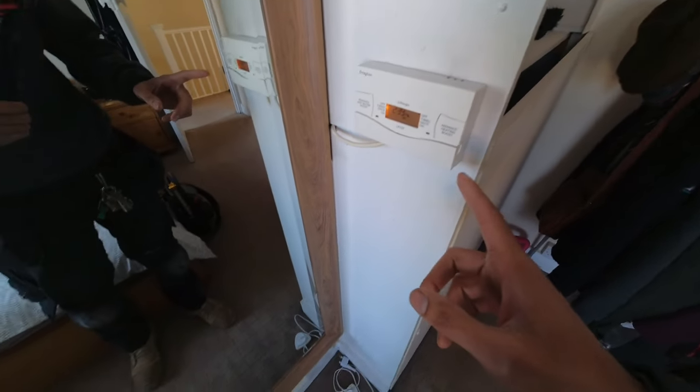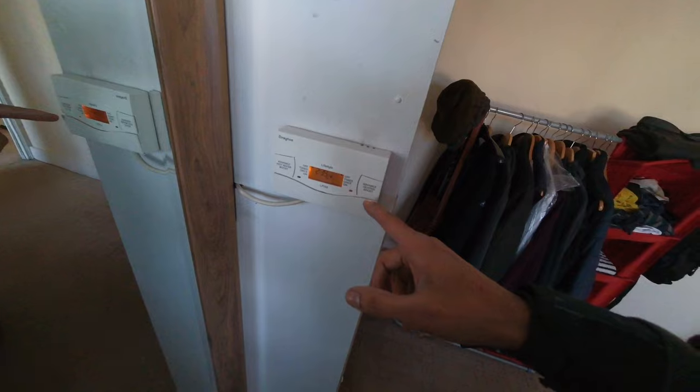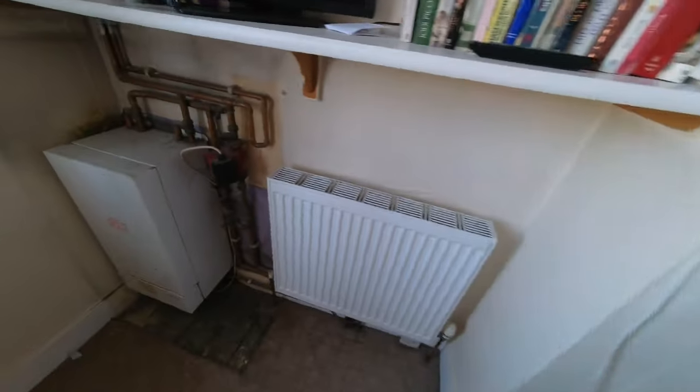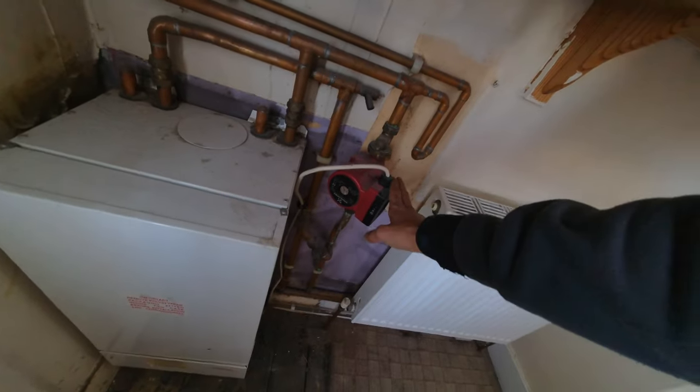Okay, so you guys might remember this one from a previous visit where the F&E tank was turned off, so there was no water in the system. Danny's called me back today because he's having some problems with heating. It's been working in the week, but since yesterday or the day before it's just completely stopped. So we're going to start at the source — start the programmer, turn that on for heating, turn the room stat up and see what's going on with the three port. I want to see that three-port motor over, see if the pump comes on, and then I'll probably go up and check the F&E tank again.